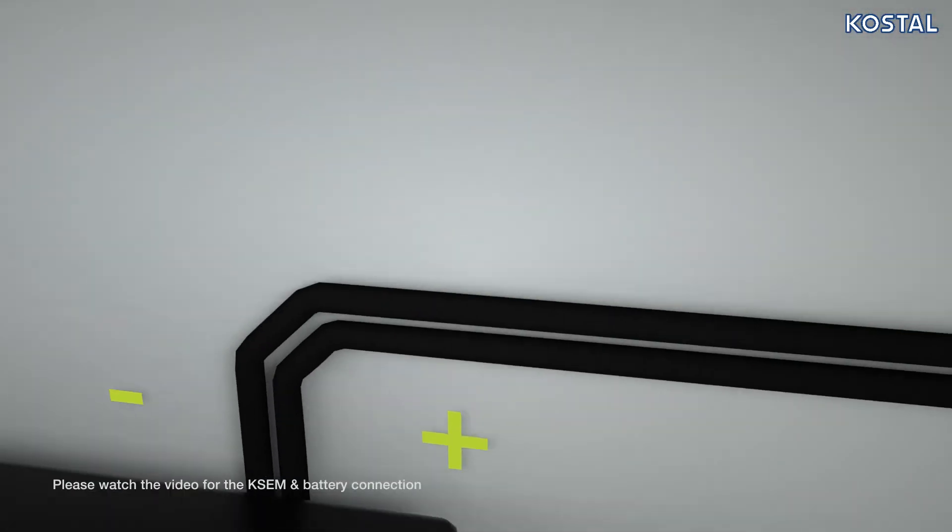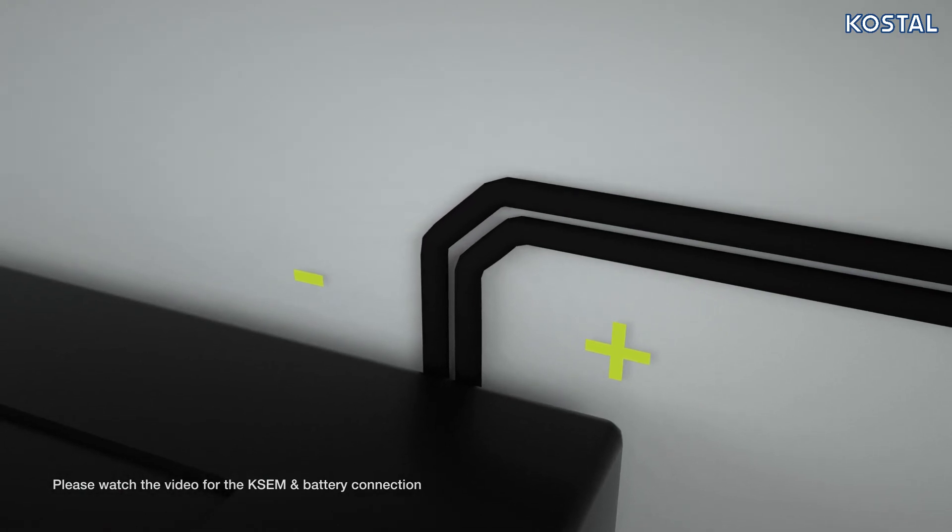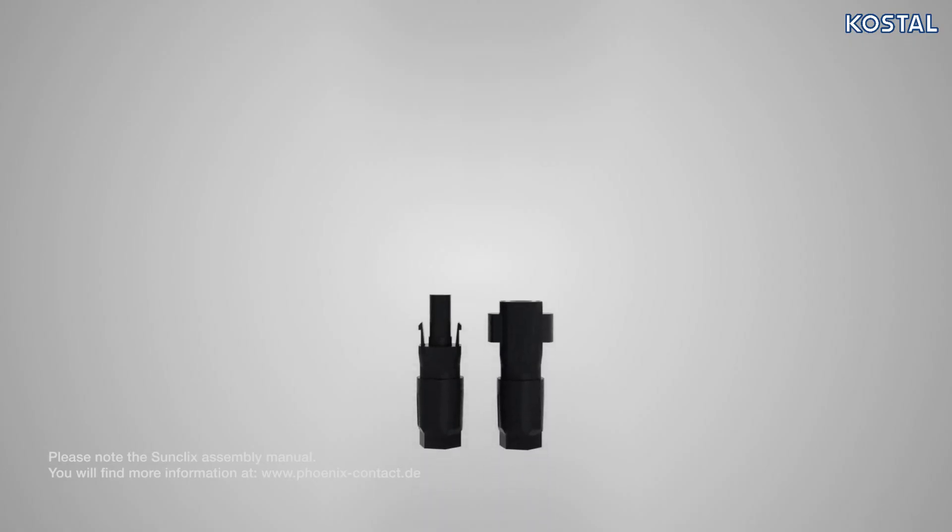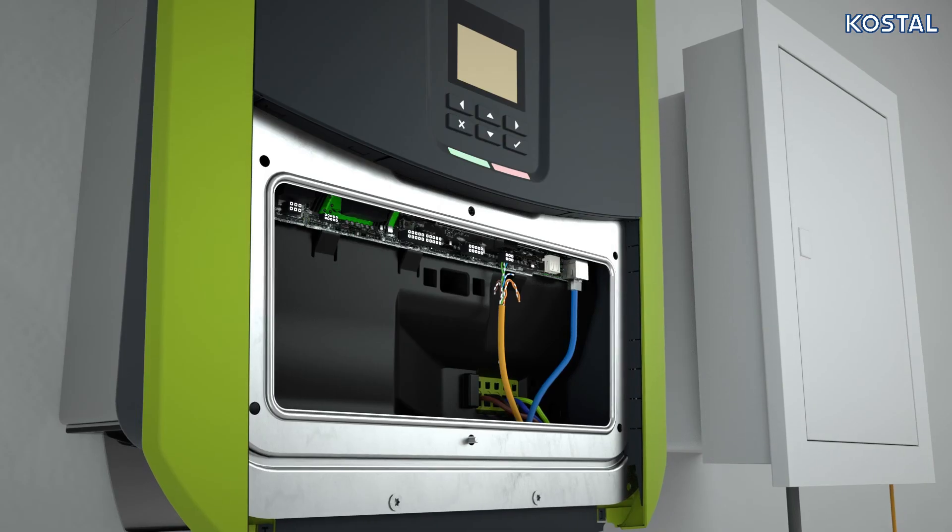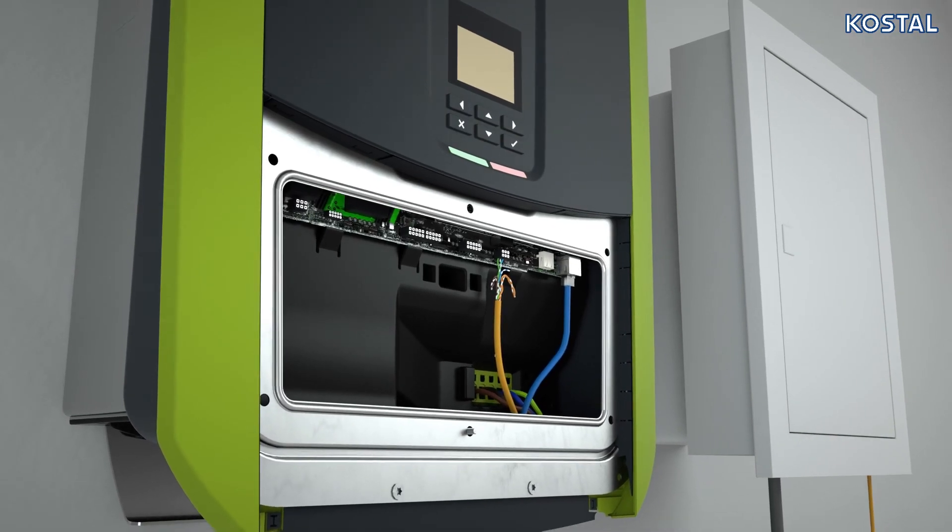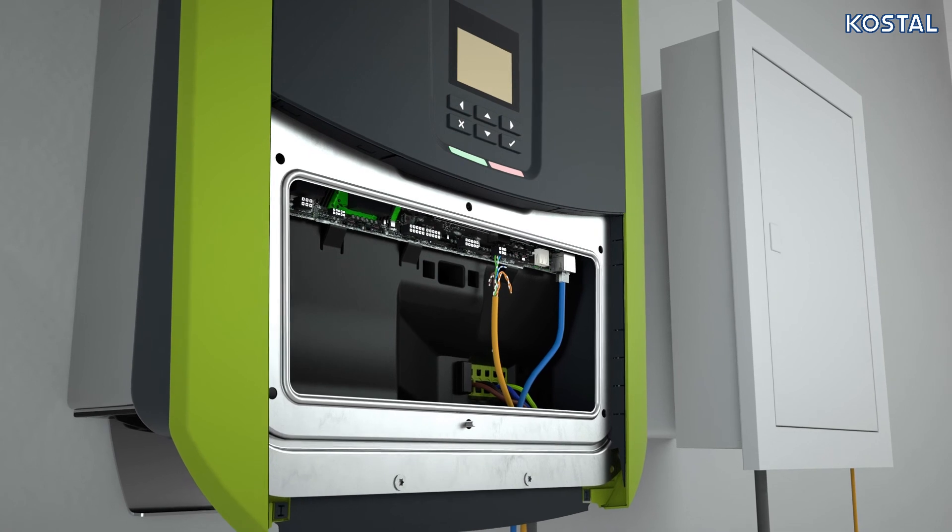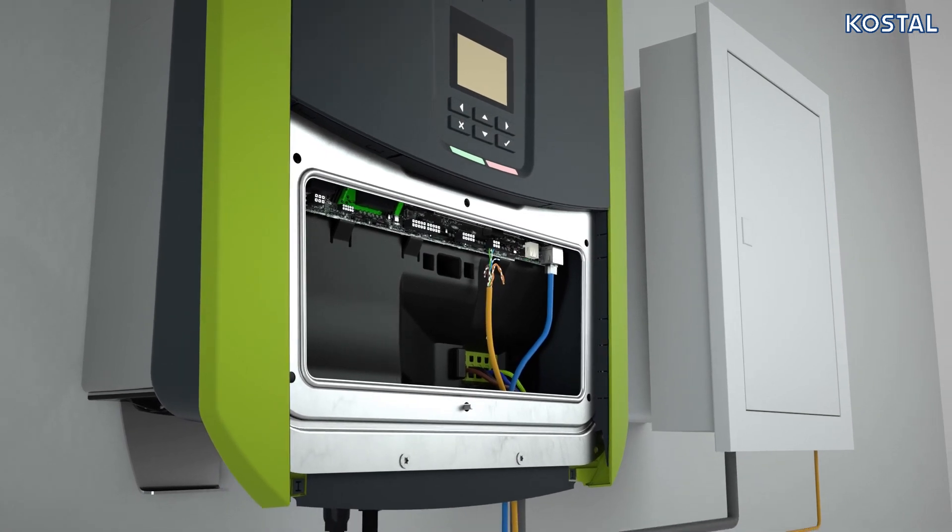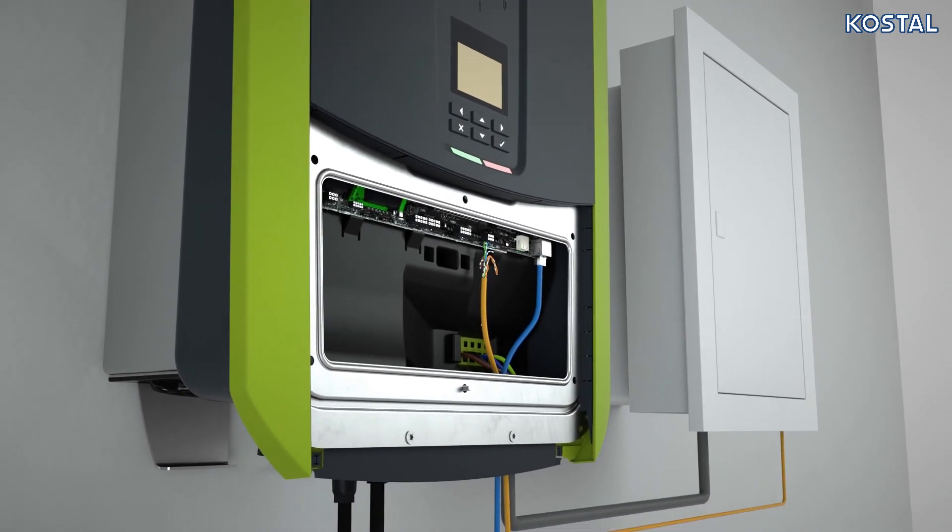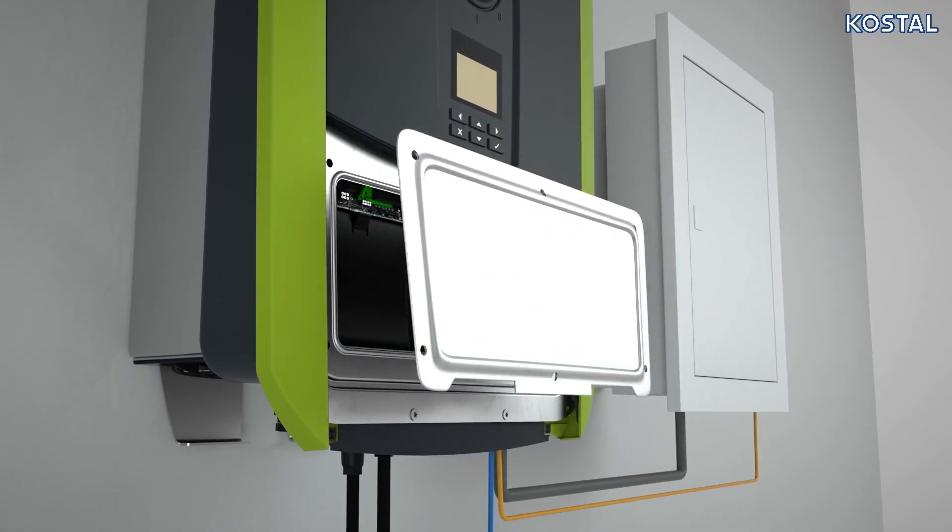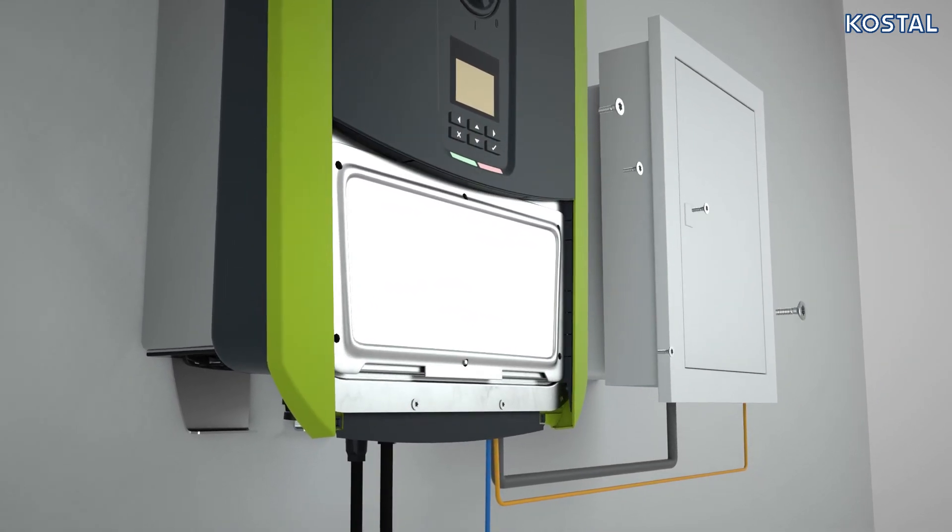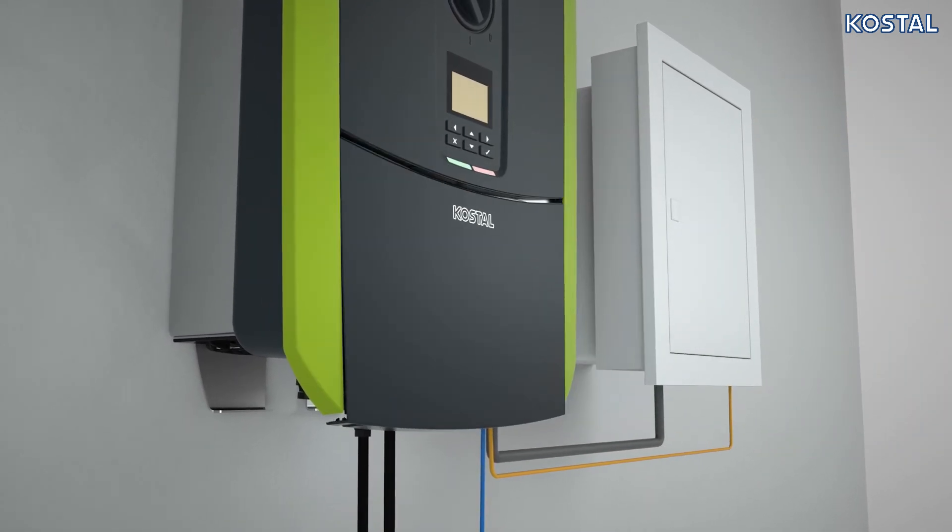Ensure correct polarity. The poles of the battery cables must not be earthed. The device uses SunClix connectors. Please use the pairs of SunClix plugs provided. Tighten all cable glands and check that they are well sealed. Screw the cover flap for the terminal compartment and housing cover back onto the inverter.